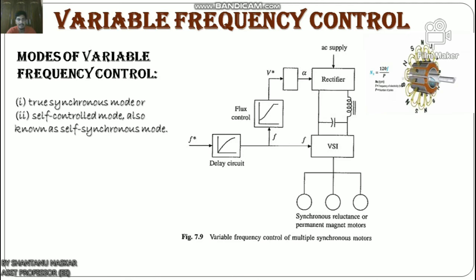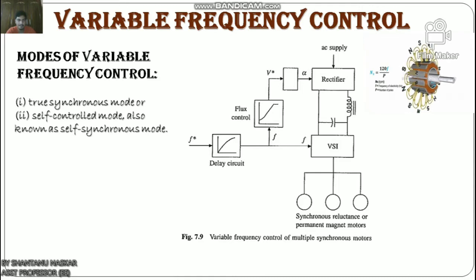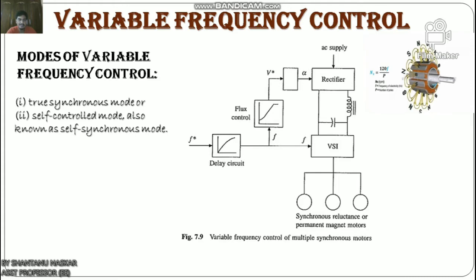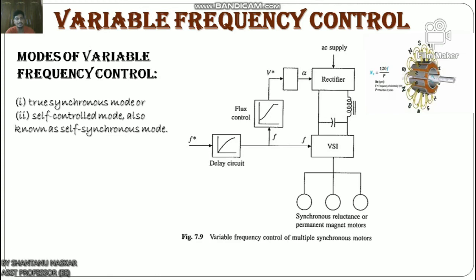This scheme is commonly used for control of multiple synchronous reluctance or permanent magnet motors in fiber spinning, textile, and paper mills where accurate speed tracking between the motors is required. Since synchronous speed is directly proportional to frequency, motor speed can be controlled by varying the frequency. Constant flux operation below base speed is achieved by operating the motor with a constant V/f ratio, which is increased at low speed to compensate for the stator resistance drop.